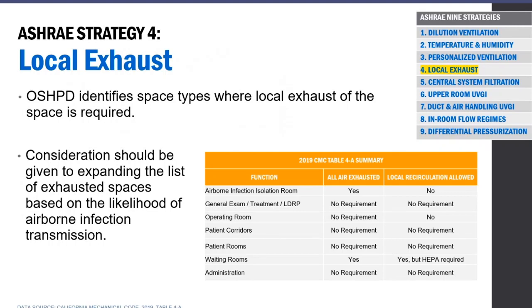We've done that in Omaha with a couple of ORs and an ambulatory surgery center, and we created our COVID unit the same way, and it worked exceptionally well. You can do it very, very quickly, and it's not expensive. Now you do have to worry about the amount of air maintaining intake or supply, so you have to do the balancing correctly and set up the exhaust and the HEPA filters, and size them correctly. But it's very effective and simple to do.